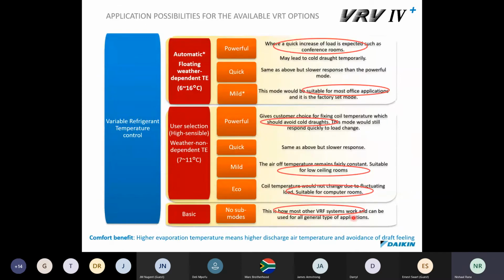Oh, sorry, I didn't touch on one more thing. The temperatures can also be used for computer rooms. Computer rooms have a high sensible load with a very low latent load. So what you actually want to do is raise the evaporation temperature of the server room, because there's no latent component, no humidity in the room to be removed. So you can go a little bit warmer on the refrigerant temperature to still achieve the correct end result without the compressors cycling on and off and tripping.